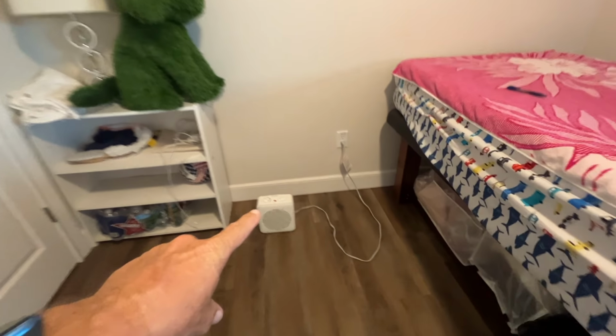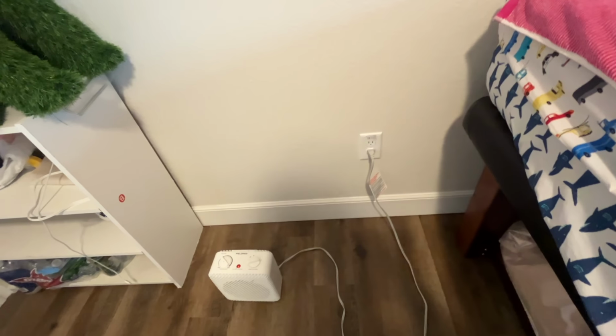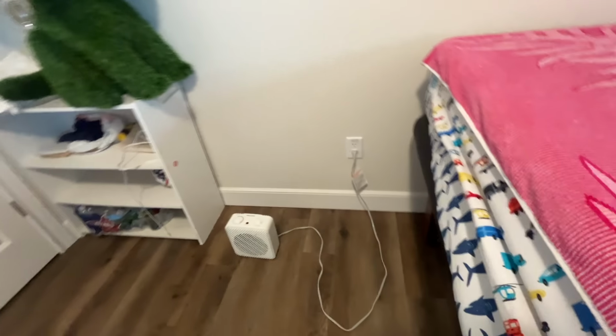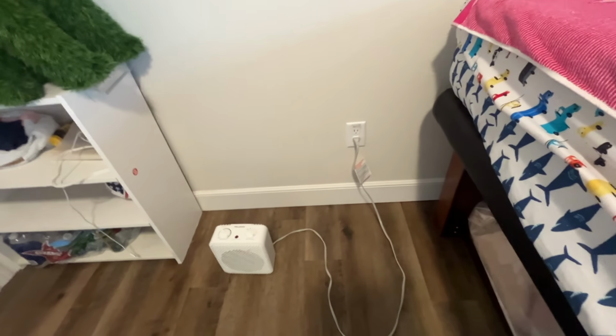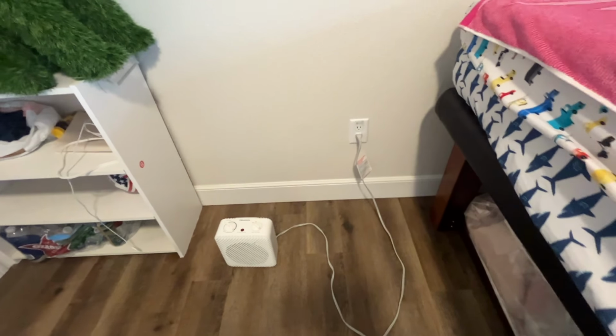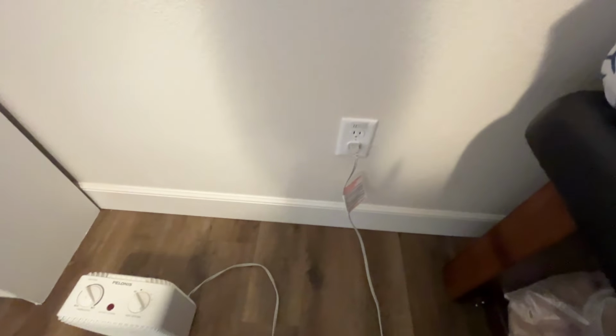If you don't plug the load into the last receptacle, and honestly I didn't know which one was last, but if you plug it into one in the middle, then the receptacles after the load would all show the same voltage, since there's no voltage drop without that high current running through them. So you'd need to move it to a spot where you are getting a drop in voltage from one to the other.